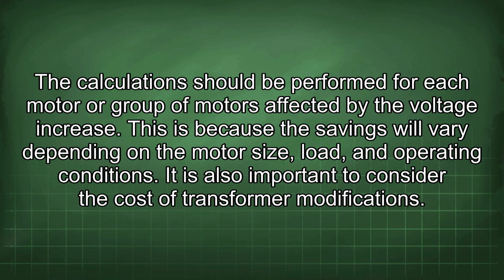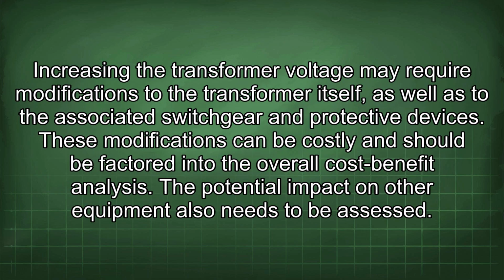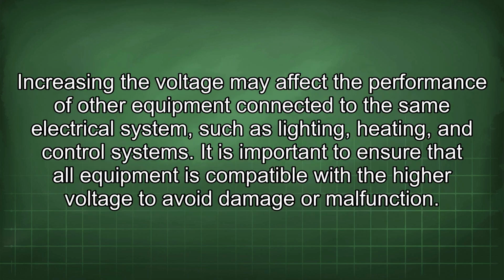It is also important to consider the cost of transformer modifications. Increasing the transformer voltage may require modifications to the transformer itself as well as to the associated switchgear and protective devices. These modifications can be costly and should be factored into the overall cost-benefit analysis. The potential impact on other equipment also needs to be assessed. Increasing the voltage may affect the performance of other equipment connected to the same electrical system, such as lighting, heating, and control systems.